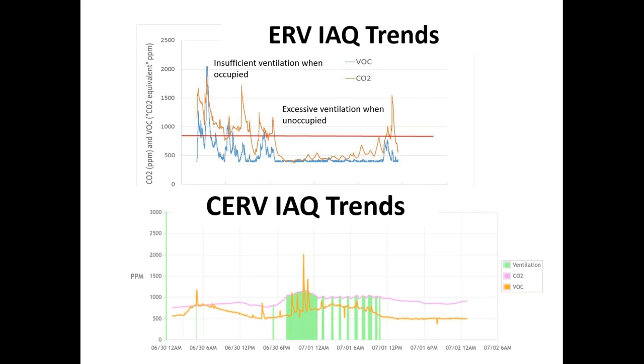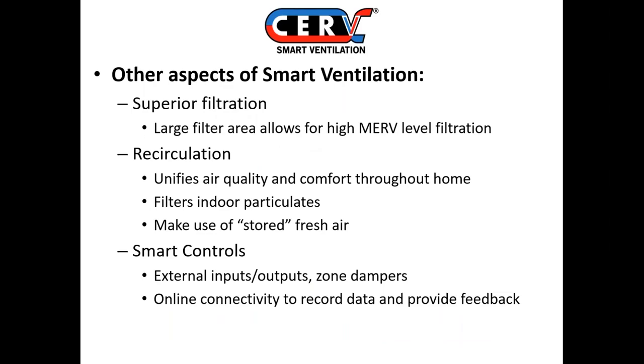Some other aspects of the CERV in particular related to smart ventilation are superior filtration. So we've kept that in mind. People ask why the unit can't be smaller. Just to maintain good airflow and good filtration, unfortunately, that means that you do need a good surface area for the air to flow through. So we have standard MERV 13 filters, but you can go higher than that if you'd like.